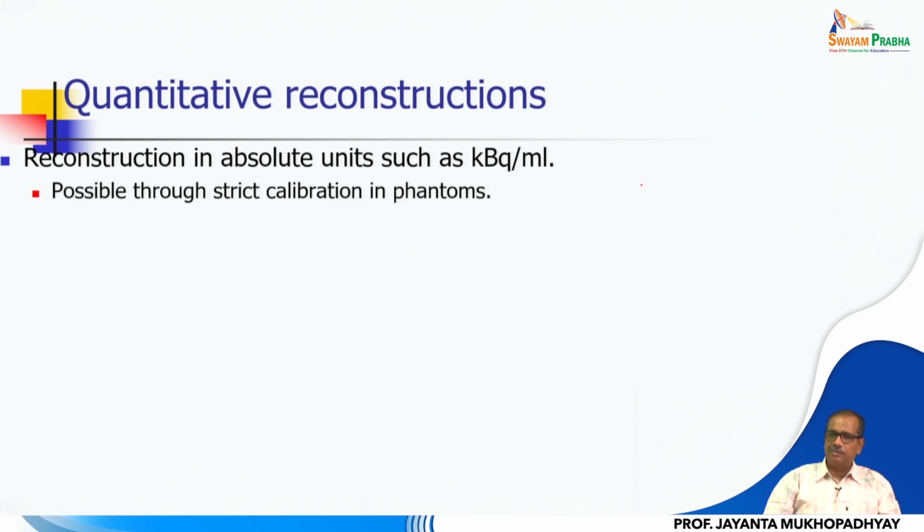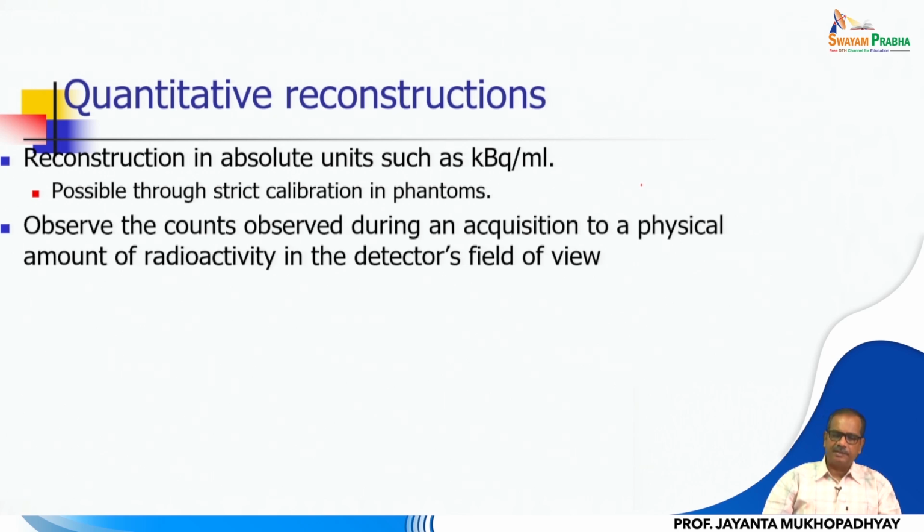We can use some phantoms. In medical devices, you can build phantoms mimicking certain tissue properties. Those are gels. You take the image and observe those measurements, either positron emission or SPECT, and then you calibrate the device with known concentrations of doses. You inject doses with known concentration, observe them, and you get the respective calibration.